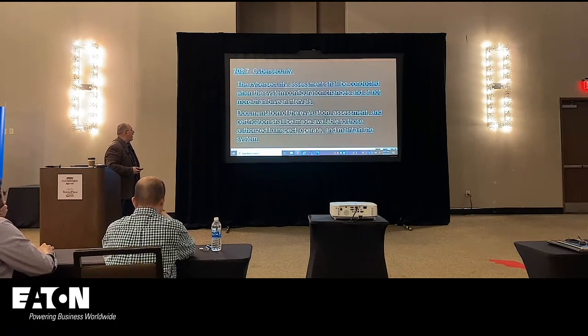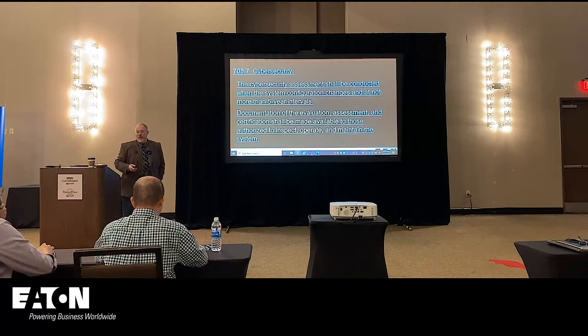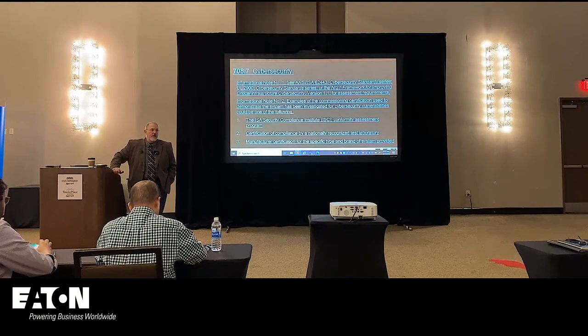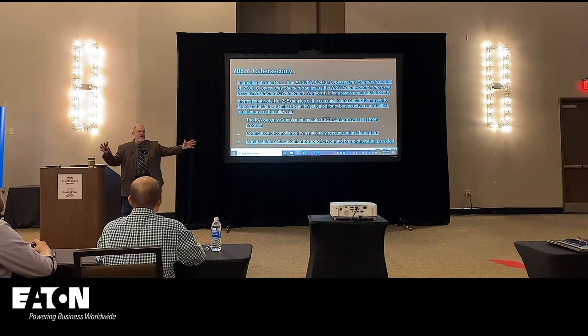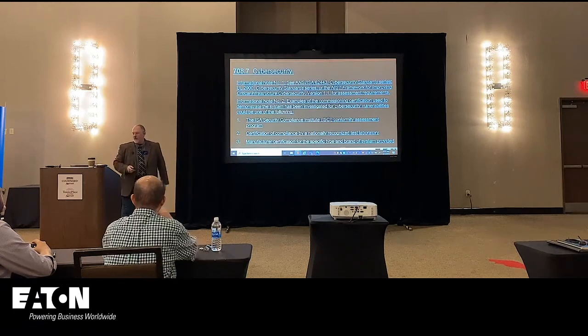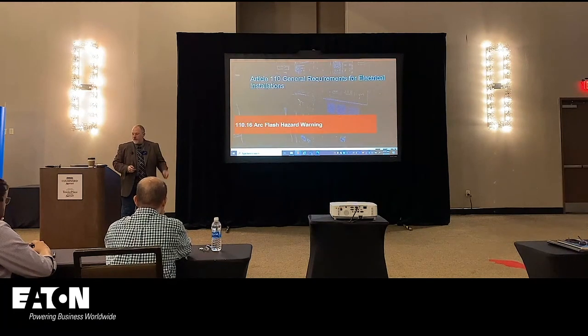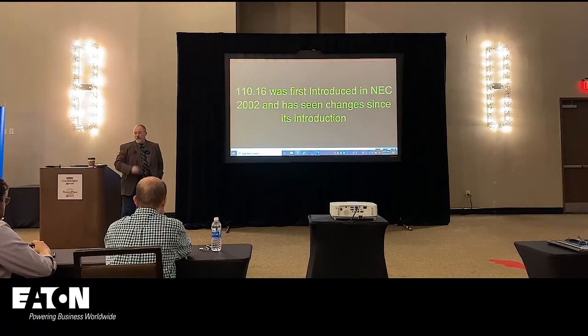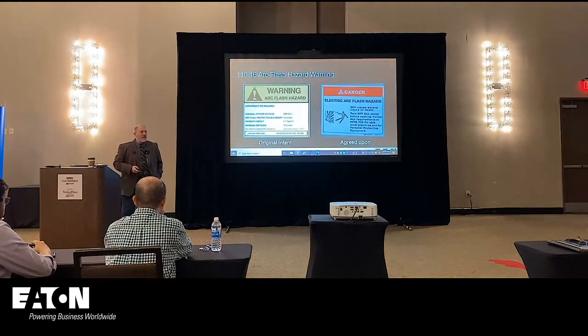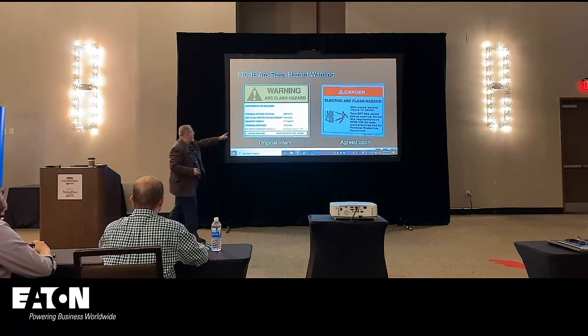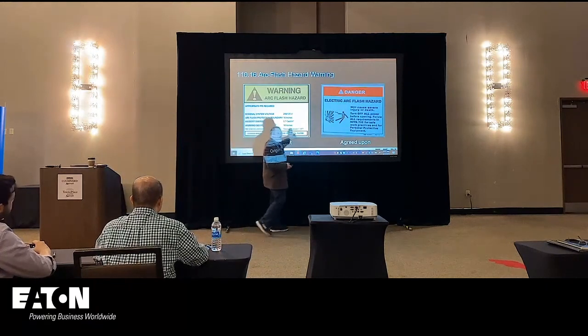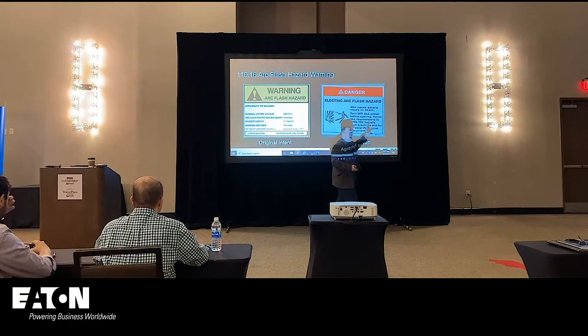Cybersecurity assessments shall be conducted when the system configuration changes and not more than 5-year intervals. And the point of a lot of the cybersecurity people is that it's not when the system changes. It's an issue regardless; your system may not change at all, and you still have a cybersecurity threat. All right. Arc flash hazards, okay, 110.16. Remember these, right? 110.16, there you had your arc flash hazard. This is your arc flash label based on 70E. This is an IEEE 1584.